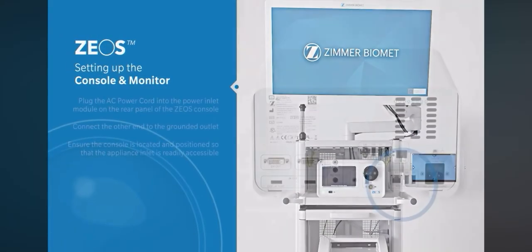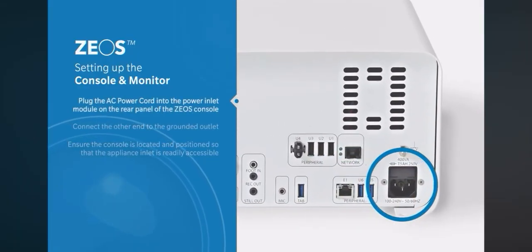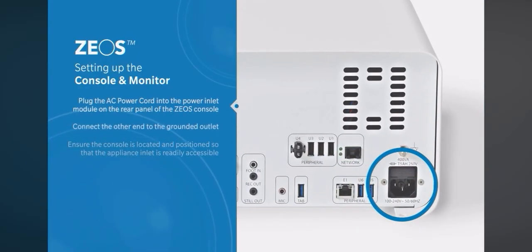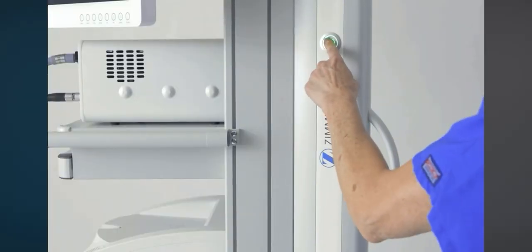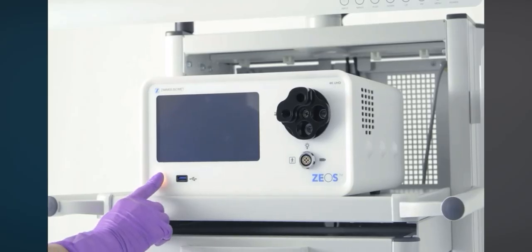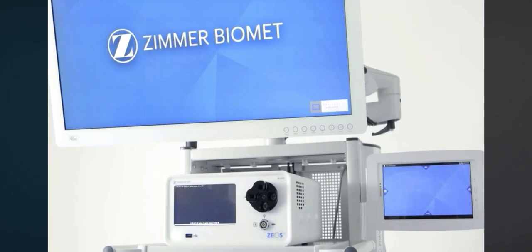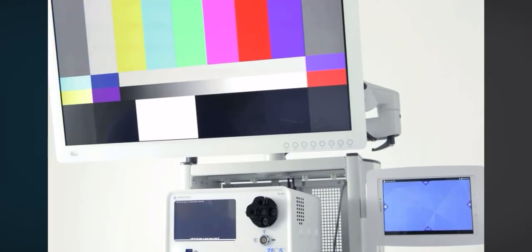To start, plug the AC power cord into the power inlet module on the rear panel of the Zeos console. Then connect the other end to the grounded outlet. Ensure the console is located and positioned so that the appliance inlet is readily accessible. After AC power is applied and the unit is powered on, ensure a color bar pattern appears on the monitor.